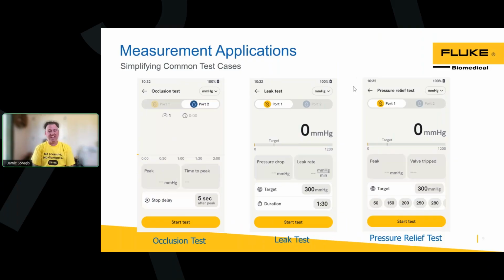Our occlusion test, right? You take your infusion pump. You can see when you hit your occlusion test app, it defaults to port 2. You would take your quick connect and run it from your infusion pump. With your infusion pump primed and ready to go, you select your rate, select your volume, and when you start your pump, the DPM5 will occlude your line, and it will calculate your peak pressure and also the time it took to get to that peak pressure.